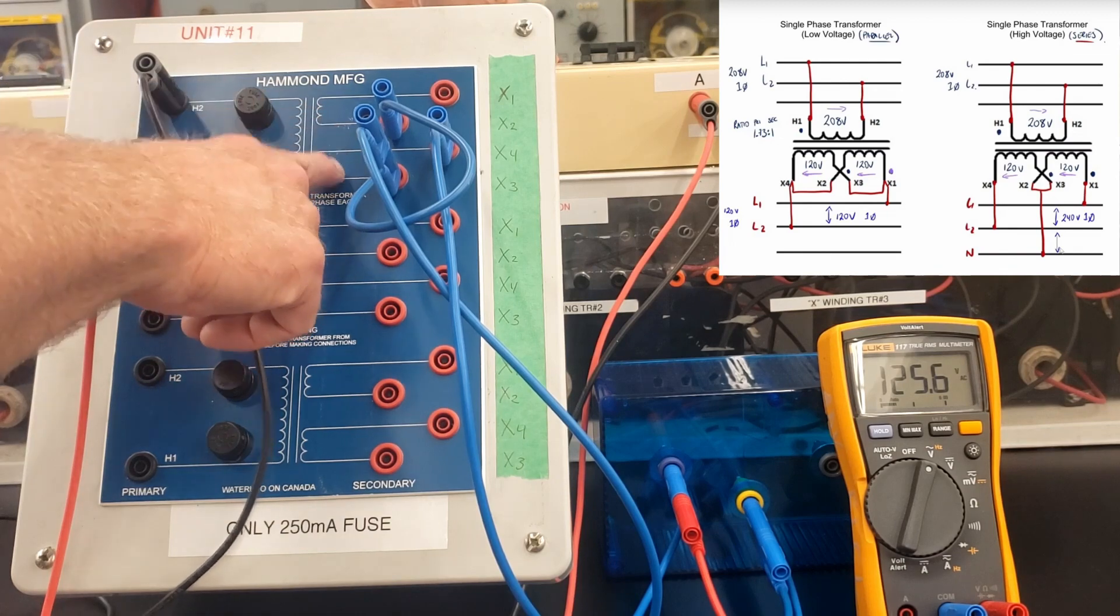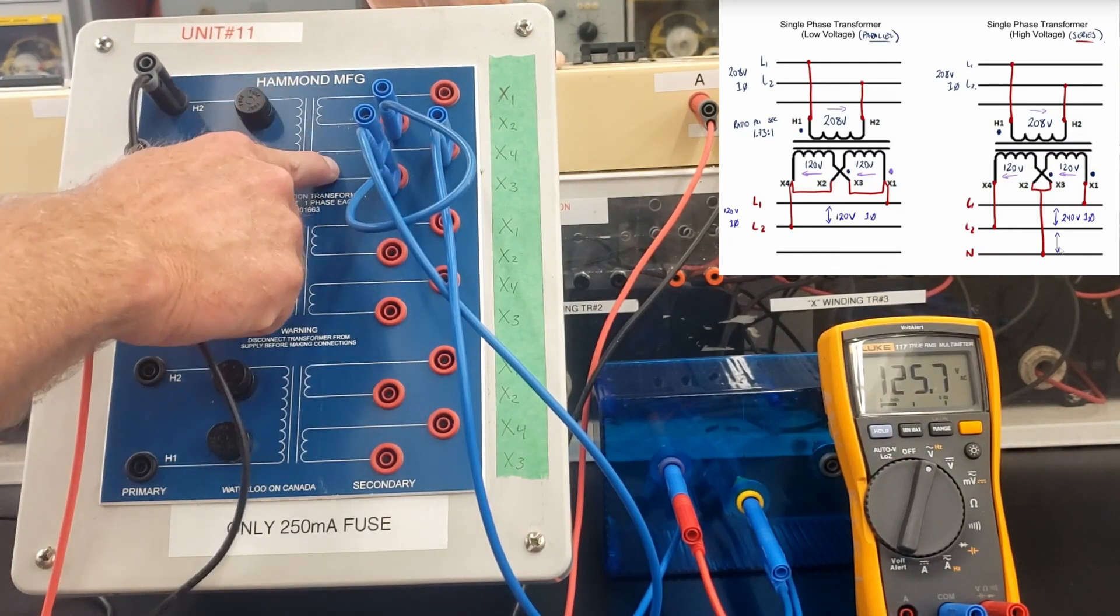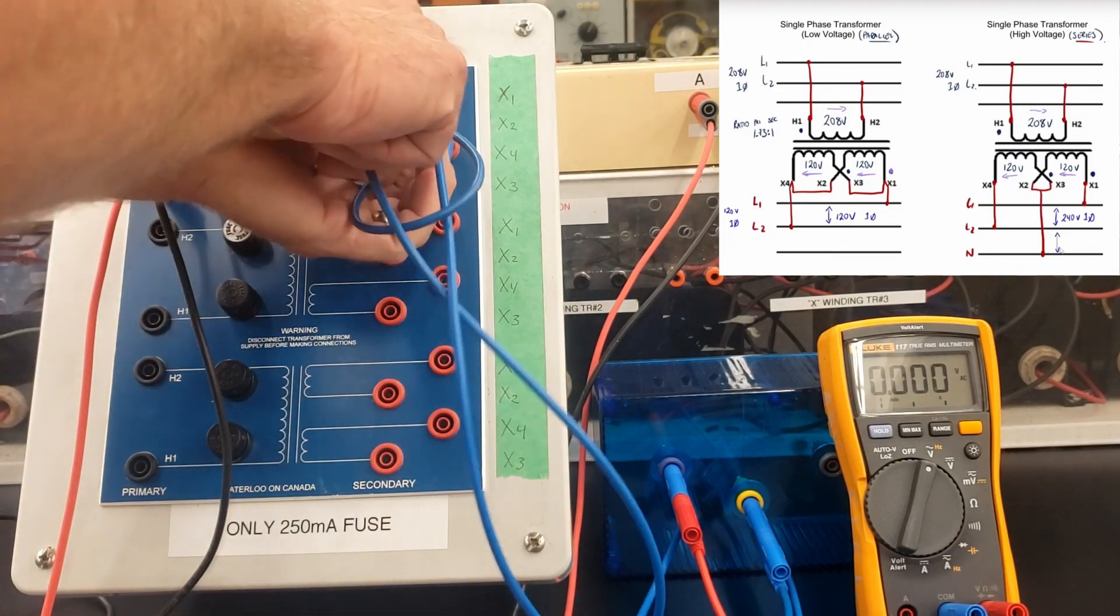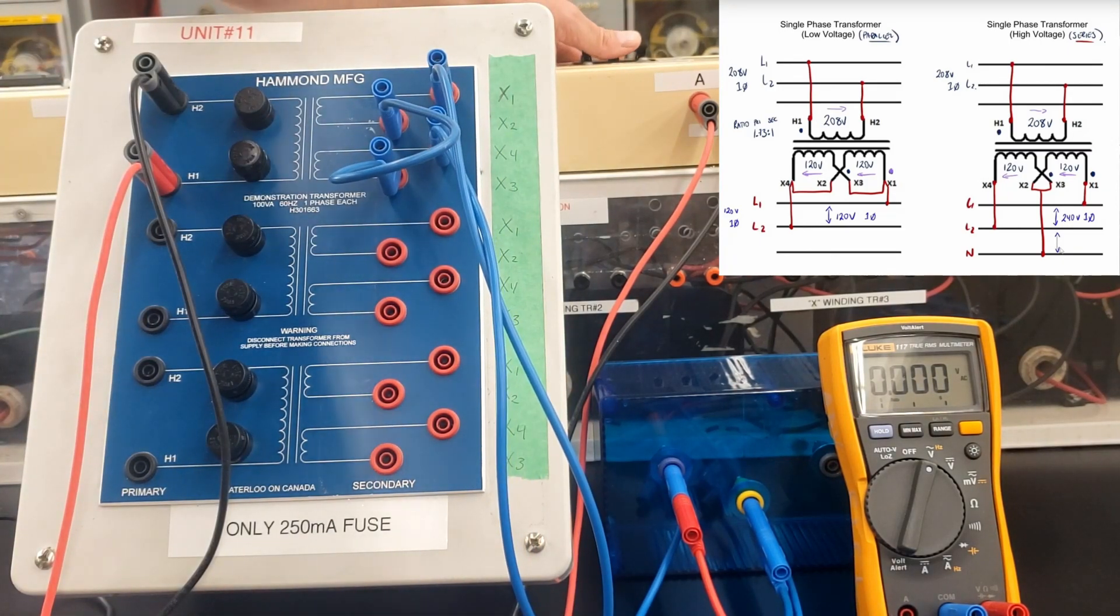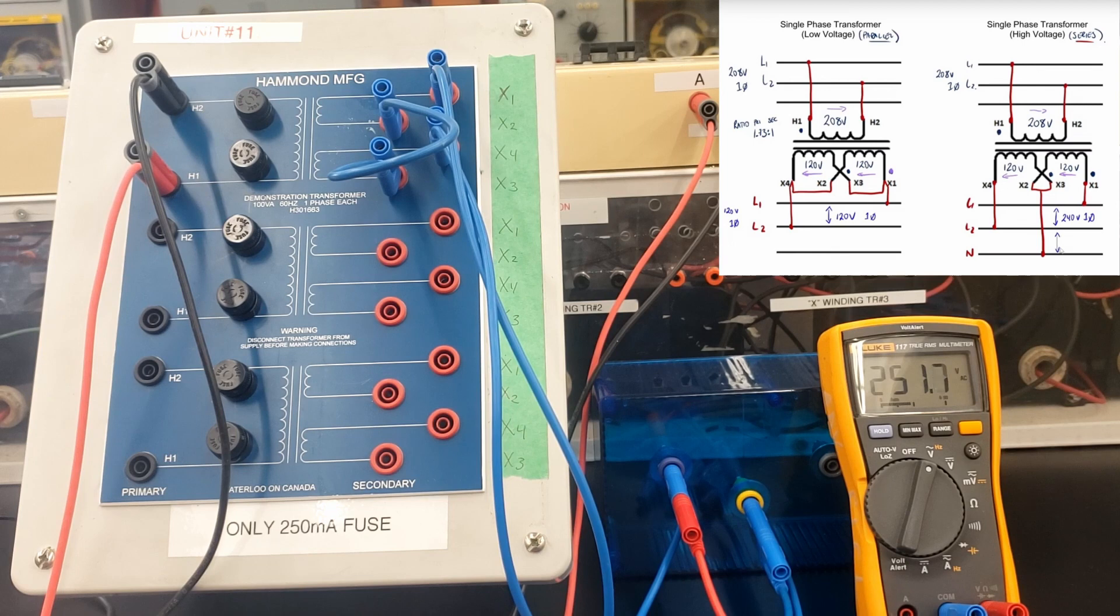Once we jumper X2 and X3, we create a series connection. And that provides us with the higher output voltage. We have 120 volts available on each of these secondary windings when we series those connections up together. Then, on the outer connections between X1 and X4, we should see the sum of those voltages being 240 volts. Again, we're seeing 250 because there's no physical load on the transformer.